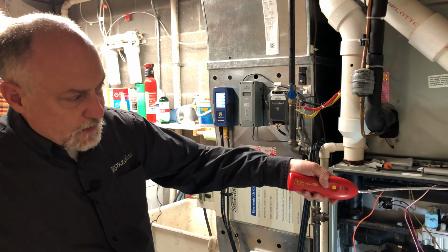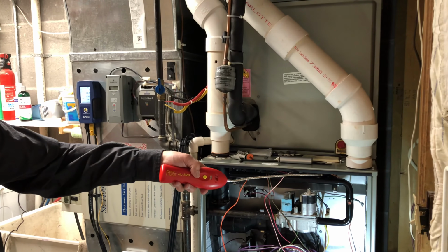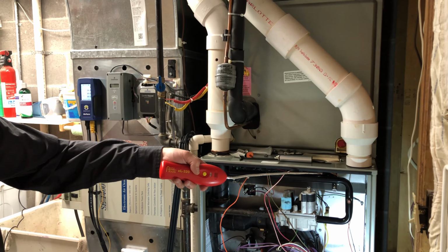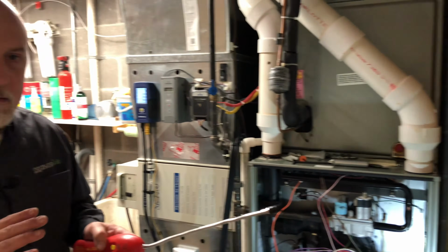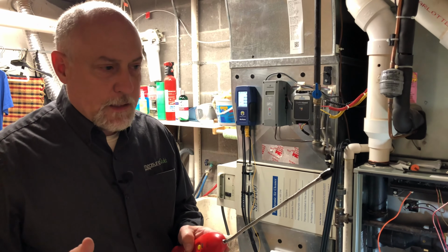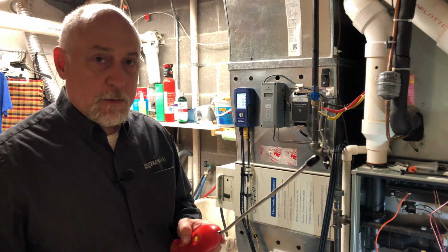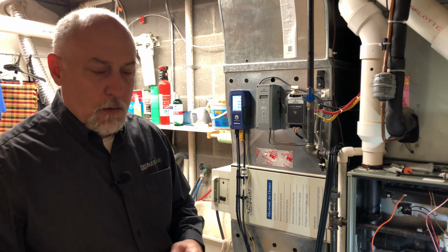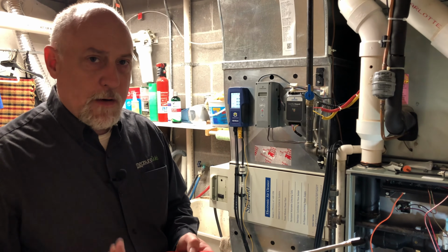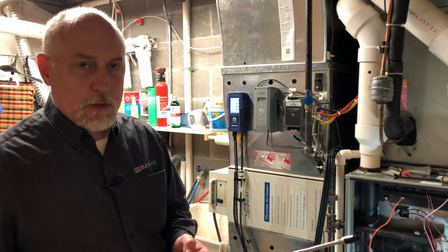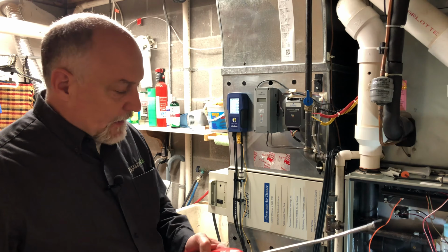If I put it on a lower sensitivity and test it again here, you can see it's not picking that up anymore. So the sensitivity on these things is just ridiculous, and it's picking up a couple little ticks there, but it is ridiculously high. So we usually test on high, and then if we find we have a leak, we're going to check with soap bubbles on low. So I'm going to turn this back to high for a second.